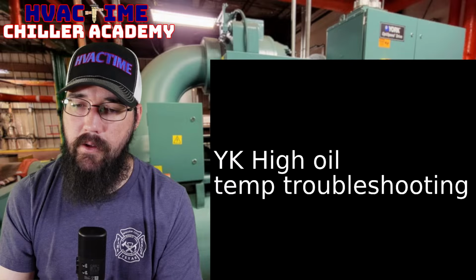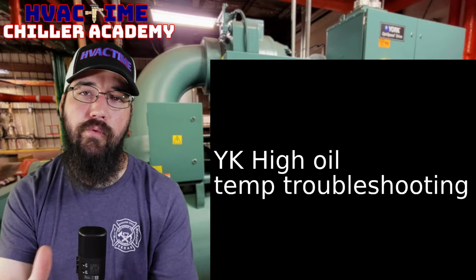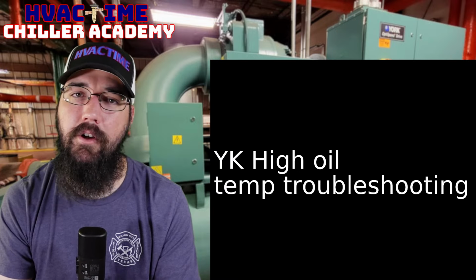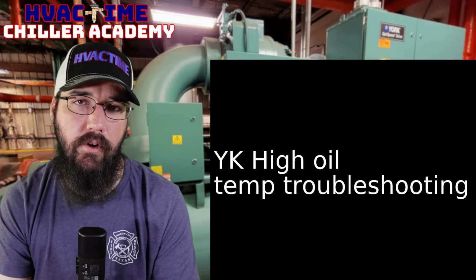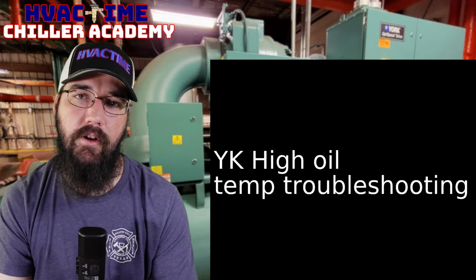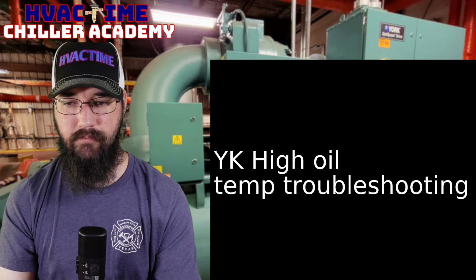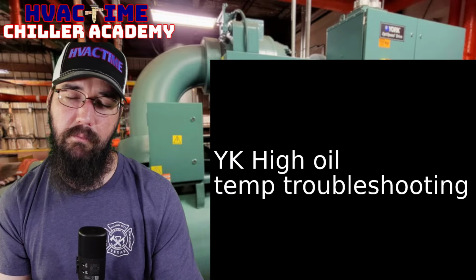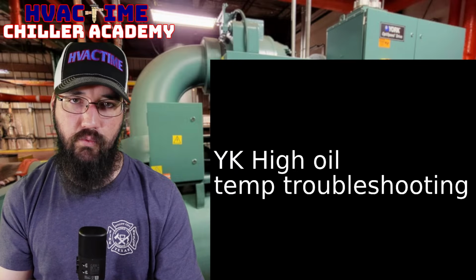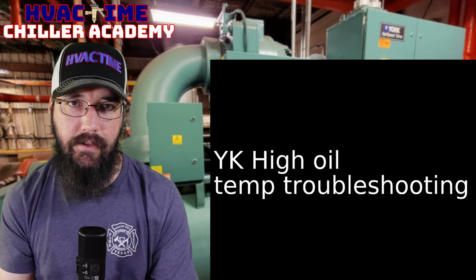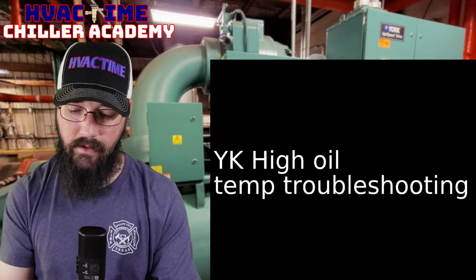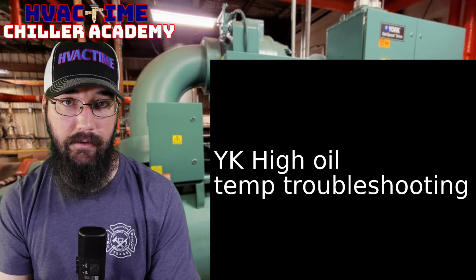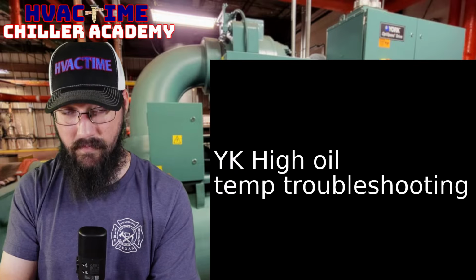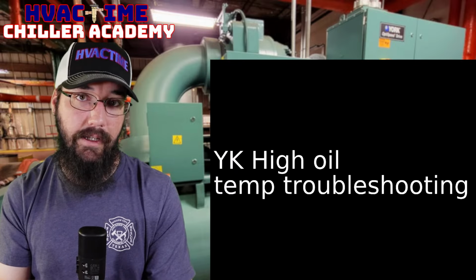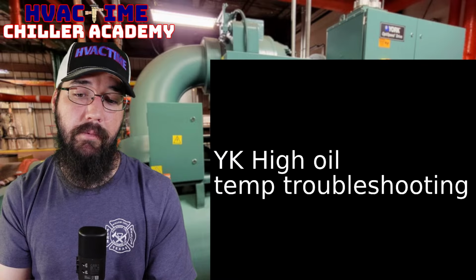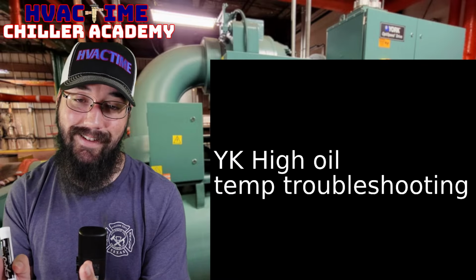I am curious. Well, we can move on. Anyway, hopefully that gives you enough to go off of so y'all can troubleshoot from there. You've already done some of it. There's just a little bit extra, especially that oil cooler being the primary. But that's why I bring up the other stuff. It's really easy to test that heater. It's really easy to test the temp sensor comparatively. And it's much easier to just look at the oil level. Those are really easy checks that take a couple of minutes. That's why I start there, and that's why I push that out first: let's get that resolved.